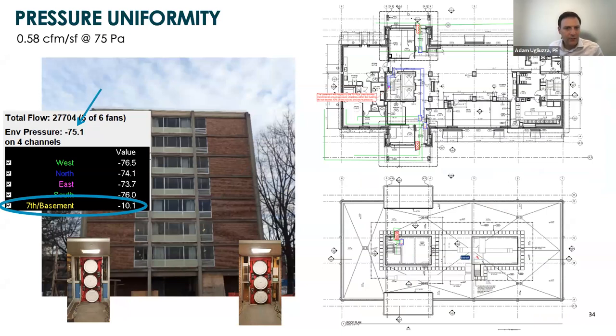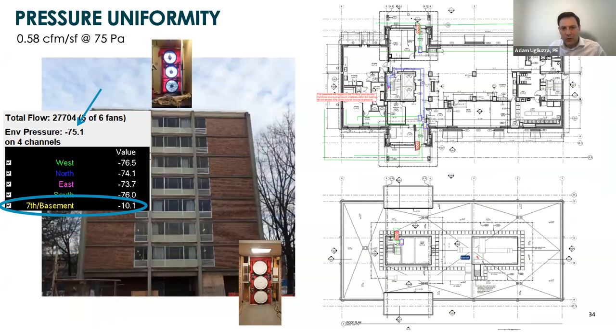Pressure uniformity, I'll spin through this. As I mentioned before, the goal is to get the building equally pressurized throughout. So you want to make sure that if you're at 75 Pascals, you have 75 Pascals across all six sides of that enclosure. And we verify that through pressure tubing to make sure that we have that uniformity.